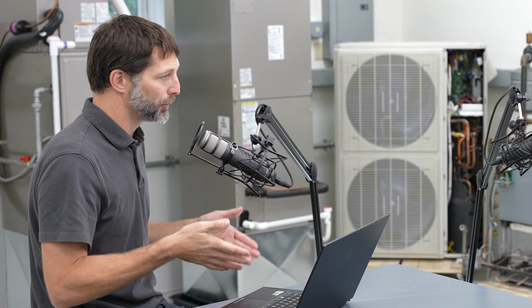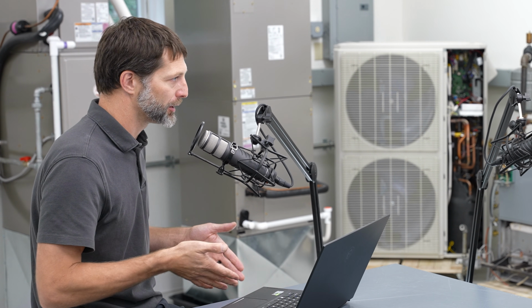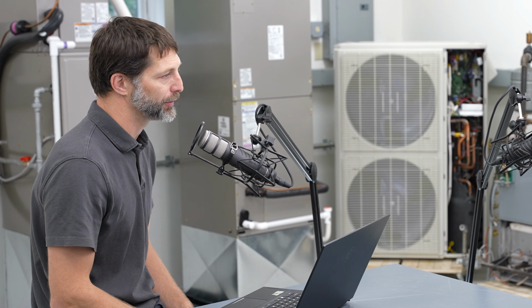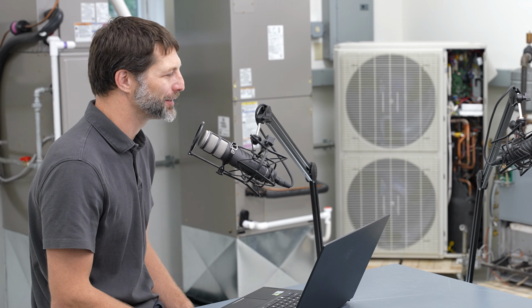Sometimes you can move the furnace out of the way, sometimes you can take the plates off. You don't have to do any of this when you have a slab coil on an air handler, because you can just get right to the back of the coil. It's great, it's awesome. But for instances when everything's super tight, you're just going to have to try your best to get to it, maybe use a fin comb brush or pull some of the dust off of it. You're going to have to be cautious with spraying cleaners or water in there, because with a vertical coil or a downflow, that water is just going to end up going into the furnace or down into the ductwork. So you have to be cautious with all these different things, and we just do our best to get that system back up and running.